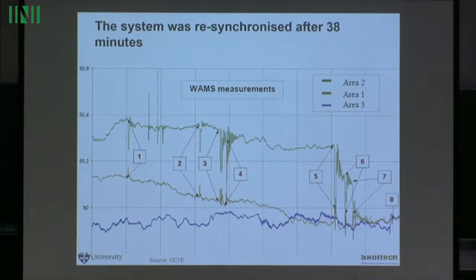You remember when I was talking about phasor measurement units - some of you were there for that. That graph was not possible for the American blackout, because those phasor measurement units, which measure frequency and are GPS synchronized in different parts of the system, were not there. But in Europe they were already there, so you can see coordinated traces of instantaneous frequency in different parts of the system. There were eight attempts to synchronize the system before they managed to do it.